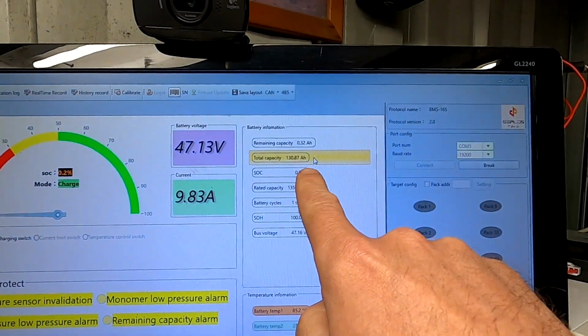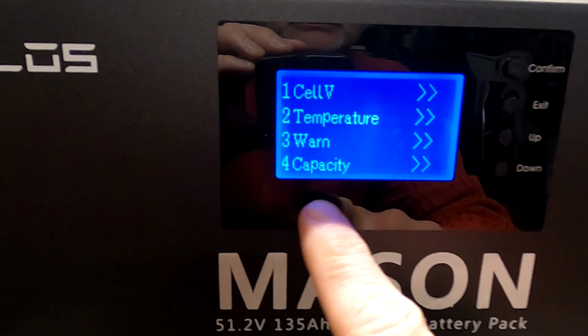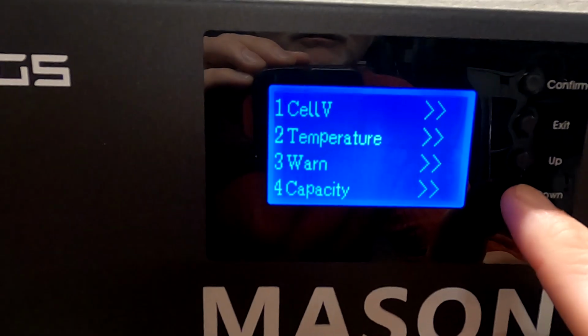If you have 1 amp for 5 hours, this gives you 5 ampere hours. 127 plus 5 ampere hours - well, we've got 130.8 ampere hours here. So we are roughly around 130 to 132 ampere hours, I would say, of the capacity out of 135 these cells are supposed to have. You can actually go to the warnings here now.